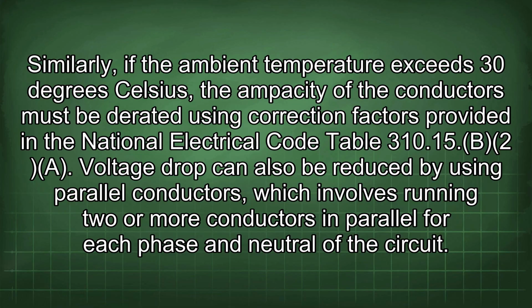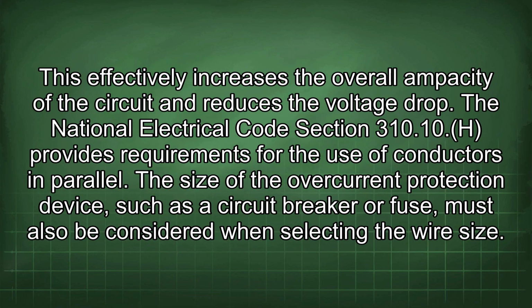Voltage drop can also be reduced by using parallel conductors, which involves running 2 or more conductors in parallel for each phase and neutral of the circuit. This effectively increases the overall ampacity of the circuit and reduces the voltage drop. The National Electrical Code Section 310.10(H) provides requirements for the use of conductors in parallel. The size of the overcurrent protection device, such as a circuit breaker or fuse, must also be considered when selecting the wire size.